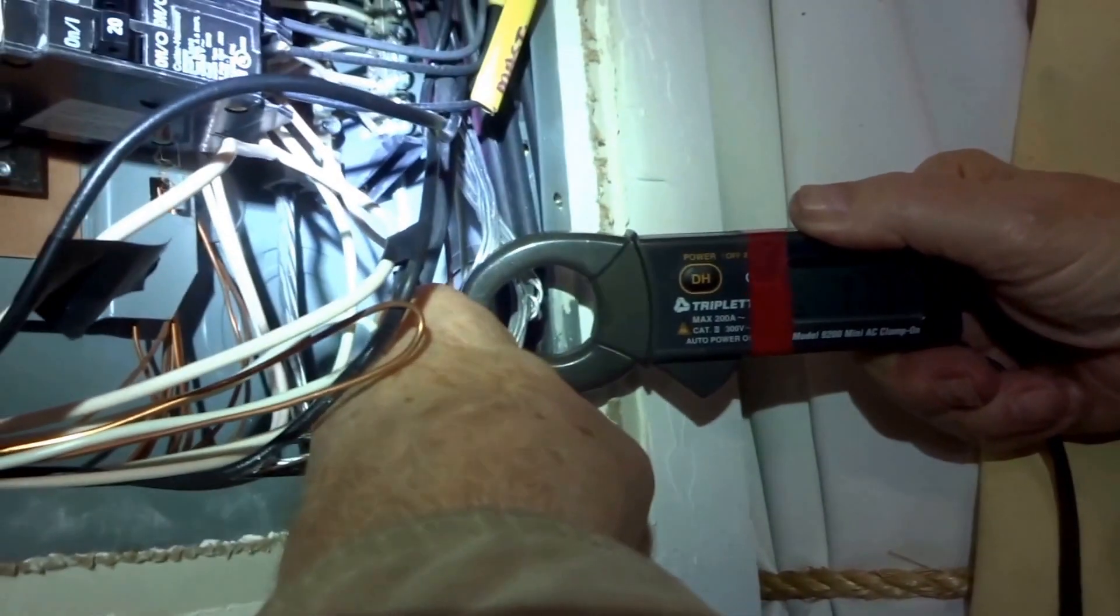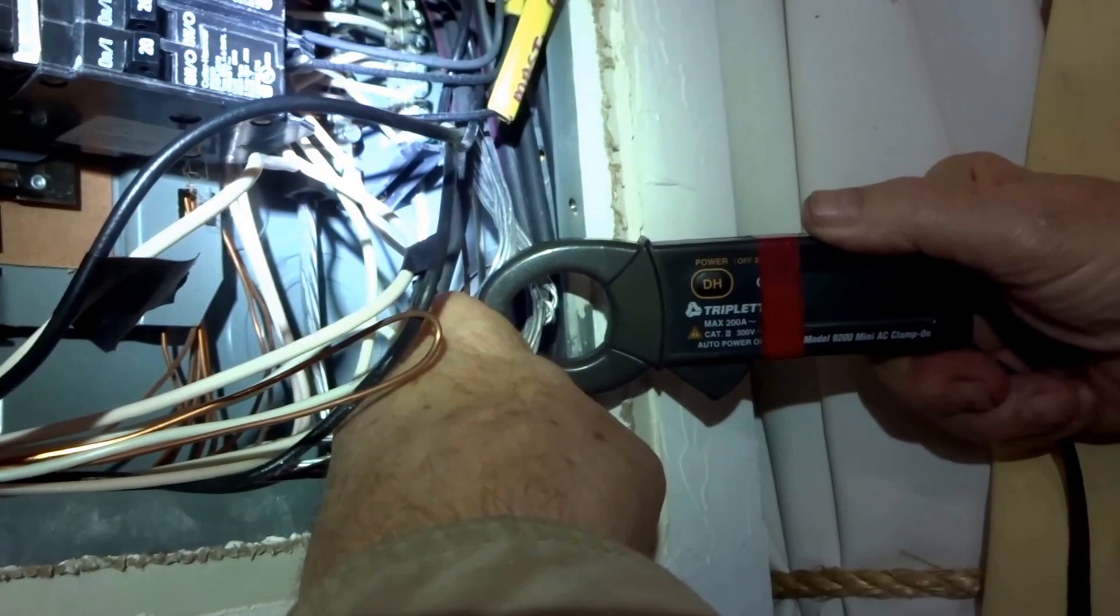I see. Almost 1.8 amps of current on the ground, and that is inappropriate. That's objectionable current. Right.